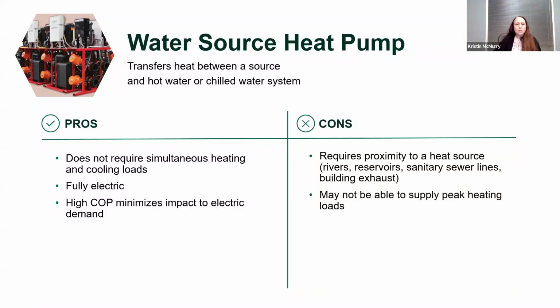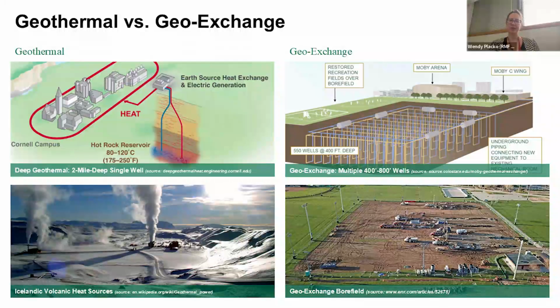The reason it's less is because you're only interacting with one system. So if you were doing the water source heat pump for your heating side, and your chilled water system was doing a water cooled chiller, your overall COP for your system might not be any worse - because on the chilled water side, a water cooled chiller is going to be like 4.75. If you add that to the COP for the water source heat pump, it might even come out higher. You have to run the numbers.